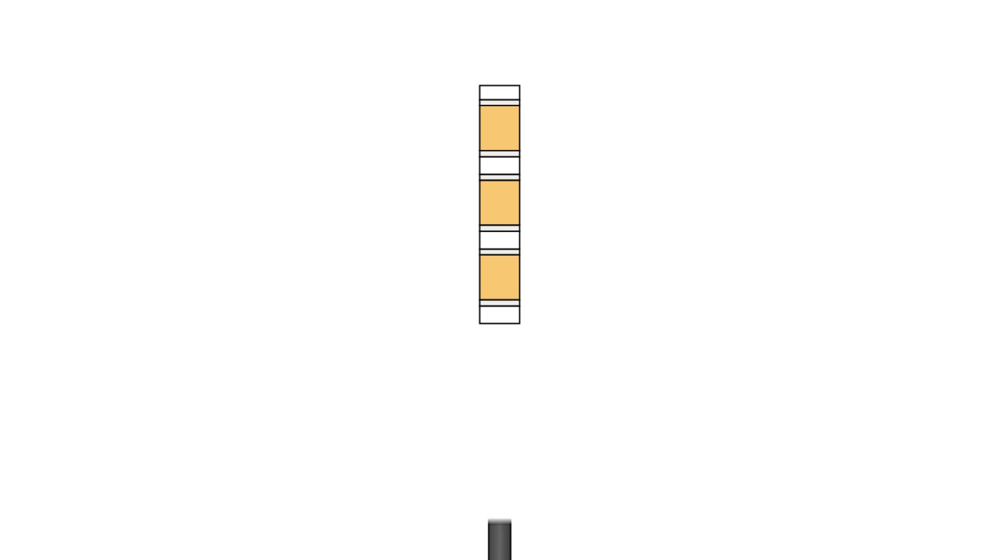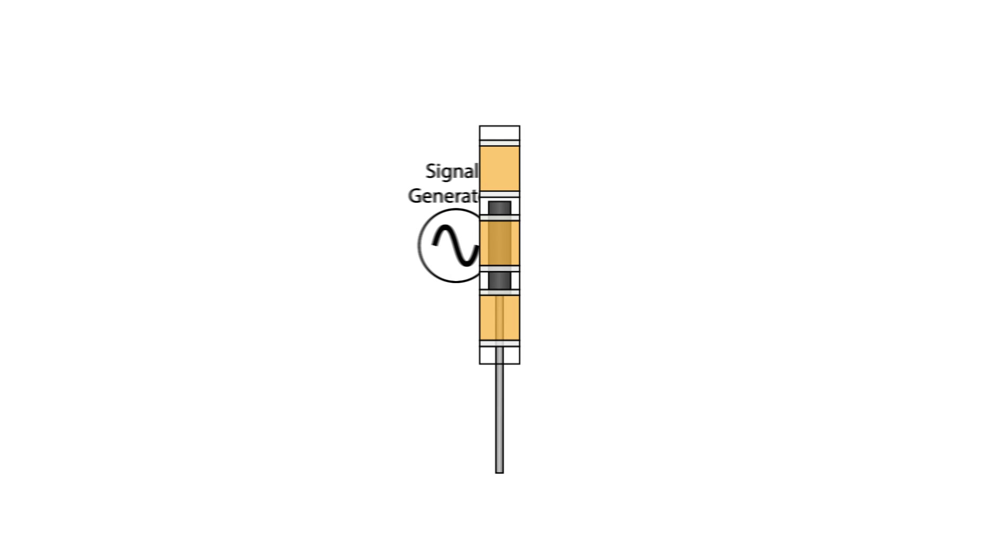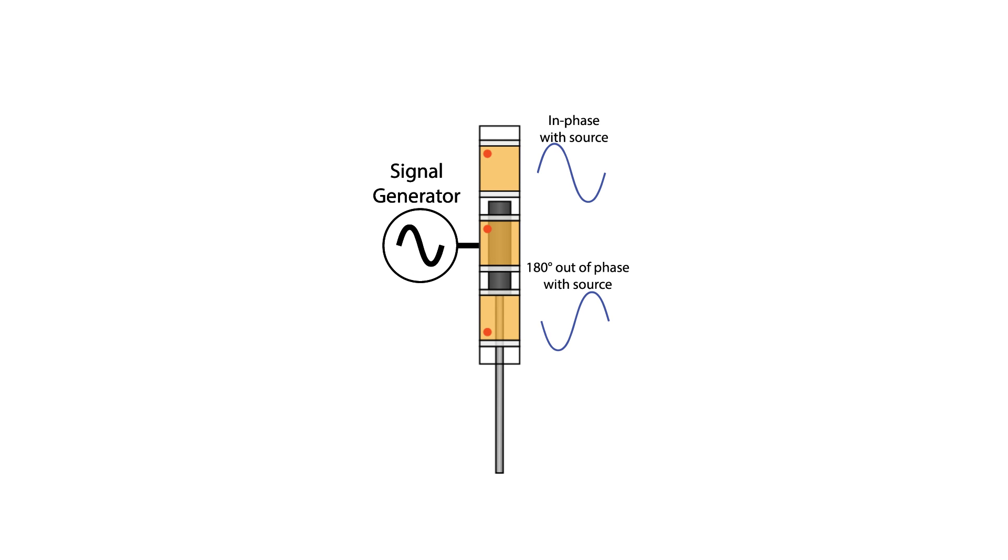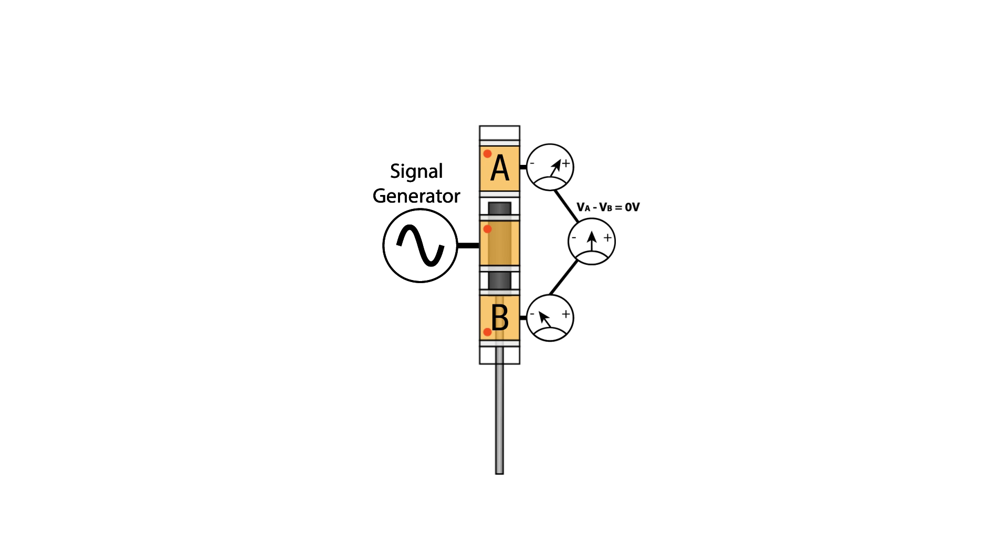To recap what's going on here, we have three coils and a ferrous rod that can travel inside of the coil form. The center coil is driven with a sine wave and there are two adjacent receiver coils. One is electrically in phase while the other is 180 degrees out of phase. Note the phasing dots and the polarity of the sine wave output signals. If we align the ferrite rod so that it's centered between the two receiver coils A and B, the mutual inductance between coils A and B are of equal magnitude but their polarity is opposite. So the net output voltage is zero.